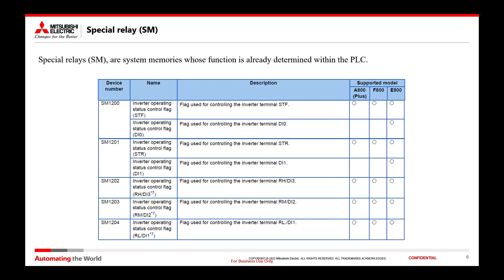The special relays represent one of the two methods available to program the PLC. Each of these system memories corresponds to a specific function already predefined within the PLC. The table below shows only an extract of all the available memories. By consulting the manual, you can find the complete list. You can see how the first SM in the table corresponds to the forward command, the second SM to the reverse command, while the subsequent memories are used to write an operating frequency to the inverter.